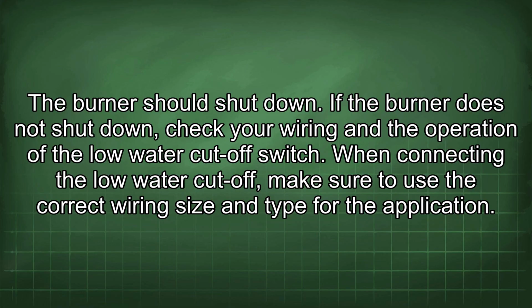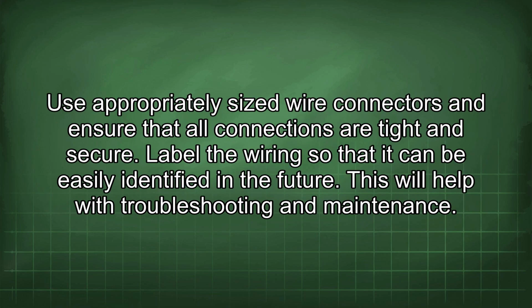When connecting the low water cutoff, make sure to use the correct wiring size and type for the application. Use appropriately sized wire connectors and ensure that all connections are tight and secure. Label the wiring so that it can be easily identified in the future. This will help with troubleshooting and maintenance.